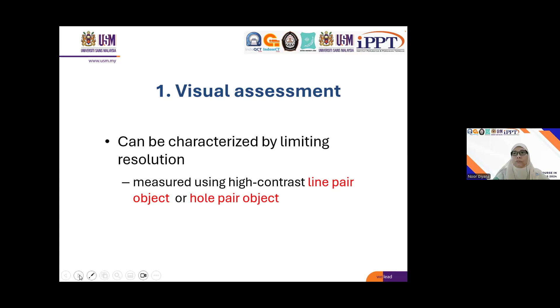So next is visual assessment. Usually it is done by measuring the line pair or hole pair objects. It can be characterized by limiting resolution. This is the visual assessment that is usually performed during the QA test. During the visual assessment, we count line pairs per distance. The phantom that we use for visual assessment consists of line pairs per distance. The line is made up of a bar, so it will appear as a high contrast line, and then separated by a gap, usually separated by equally wide space. For example here, it is 4 lines per mm.